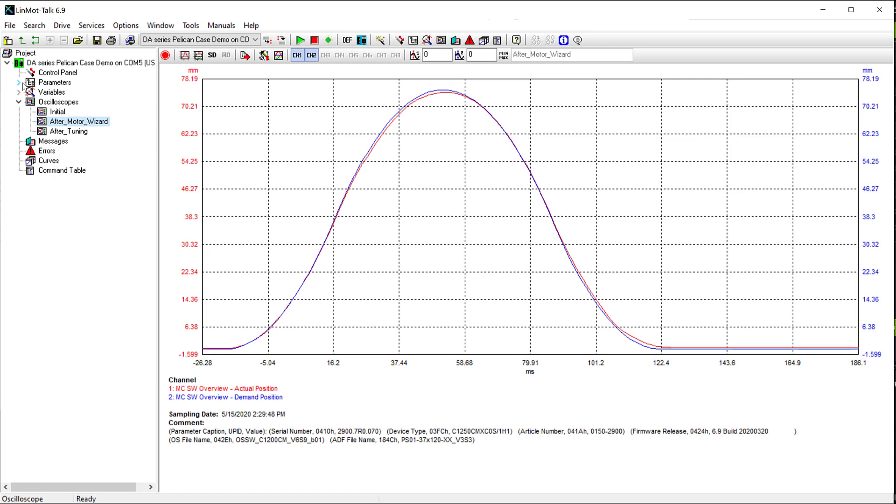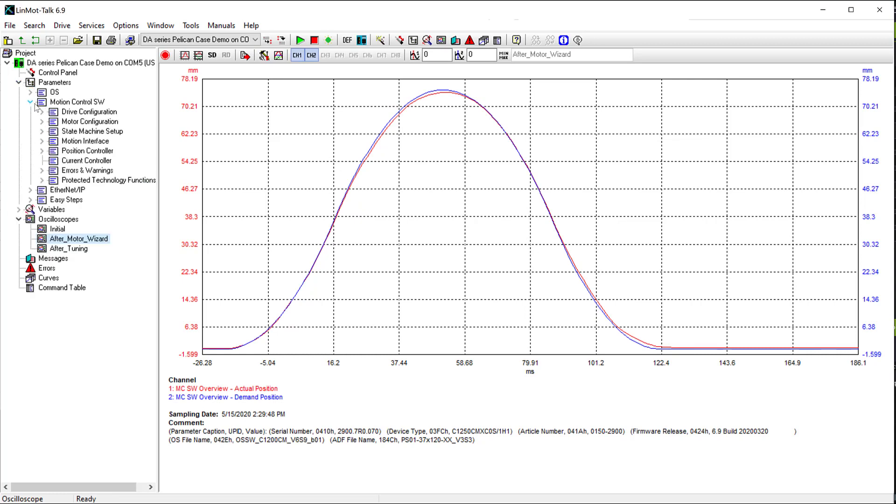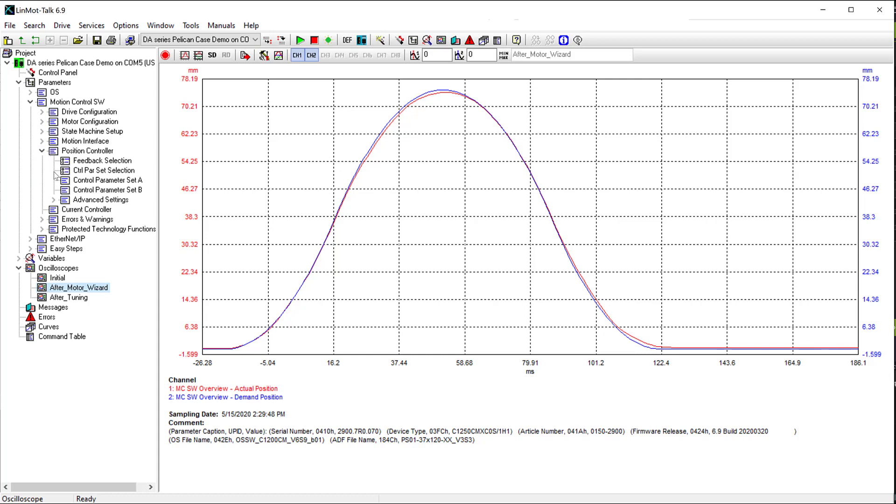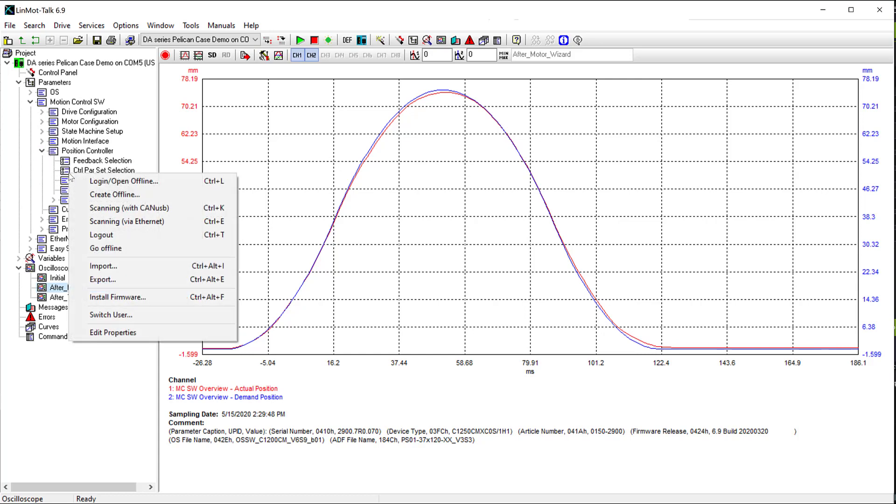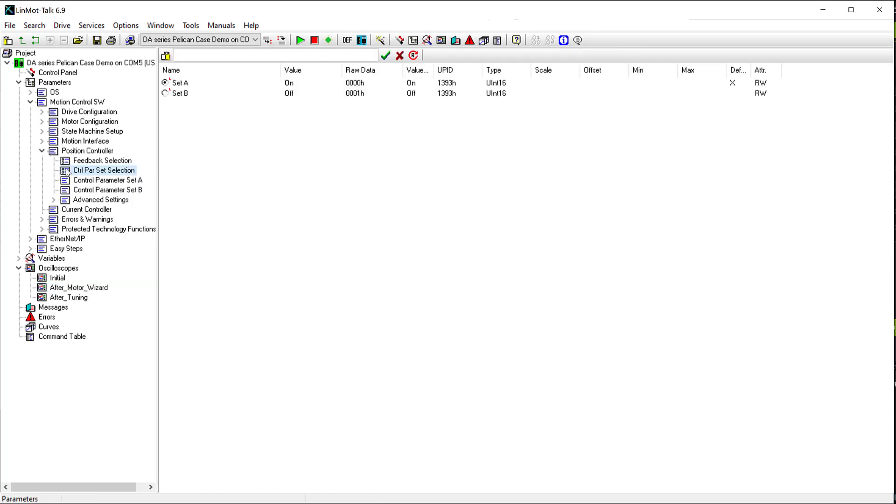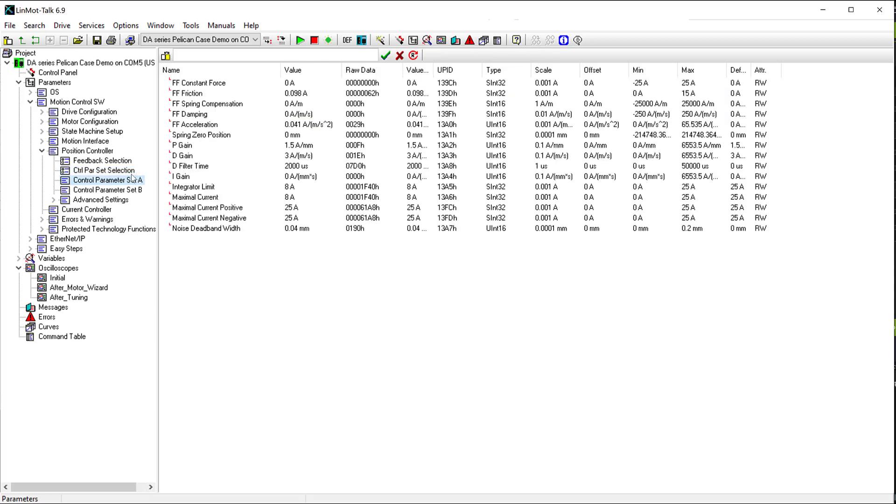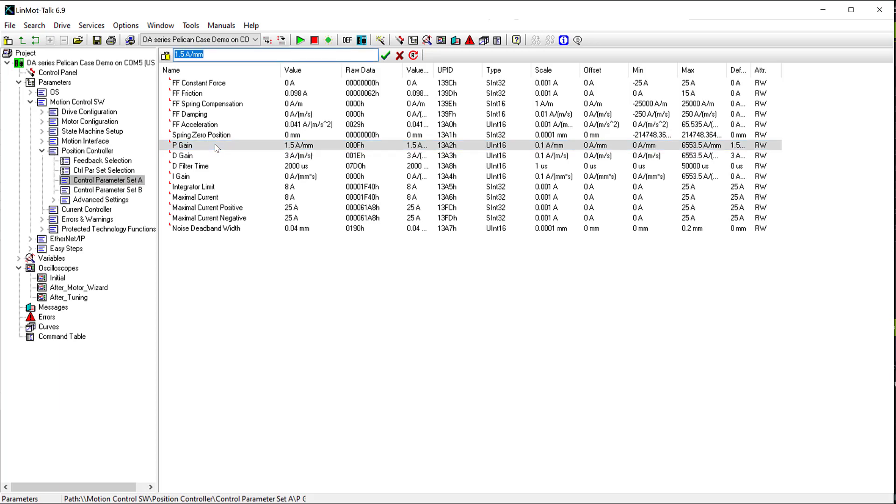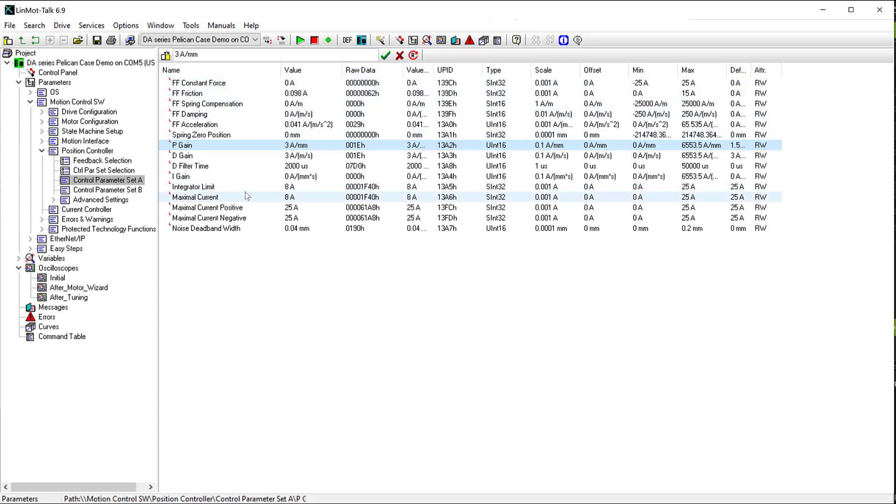So next, we will go to the PID parameters, because we see that it is lagging slowly from the demand position. So we'll go to Motion Control SW, Position Controller, and then Control Parameter Set Selection. We see that it is set to Set A. So we go to the parameters for Set A, and we'll try increasing P to 3 amps per millimeter. So now it should follow a little more tightly with the demand position.